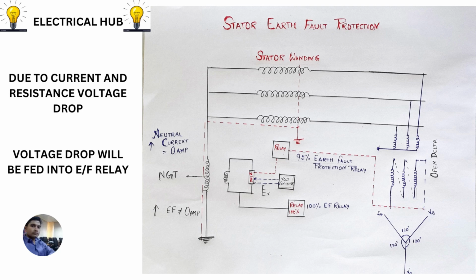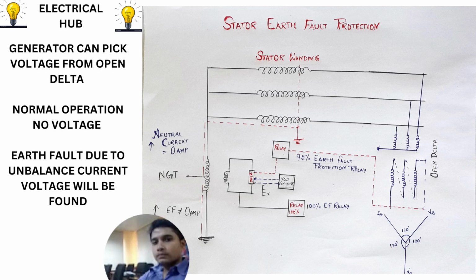As the current is flowing and there is some resistance, there will be some voltage drop, and that voltage drop will be sensed by the relay, and it will trigger a tripping. So this relay is voltage sensitive. Sometimes another method called open delta is used, or sometimes both methods are used.